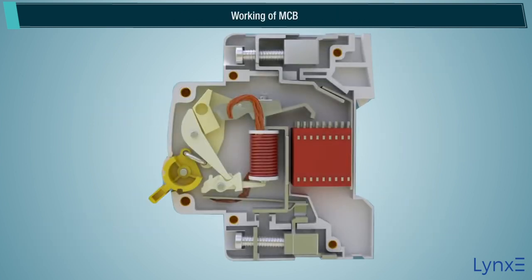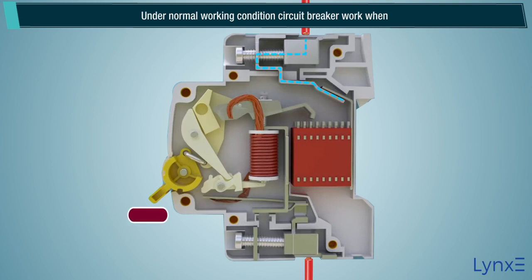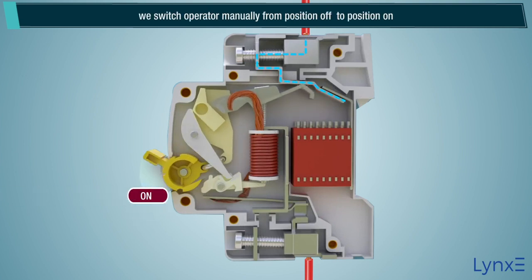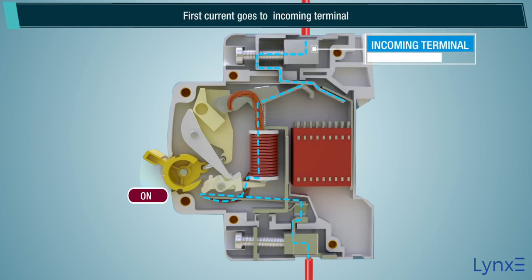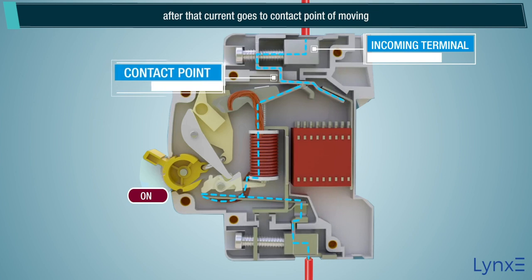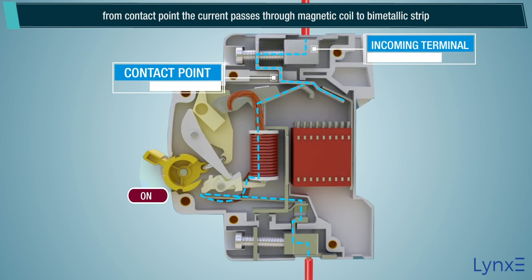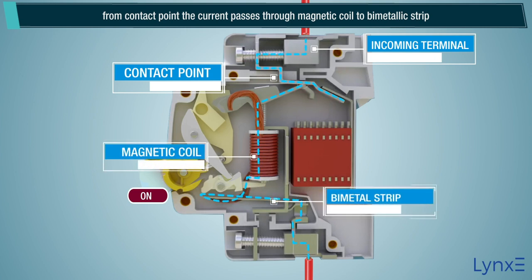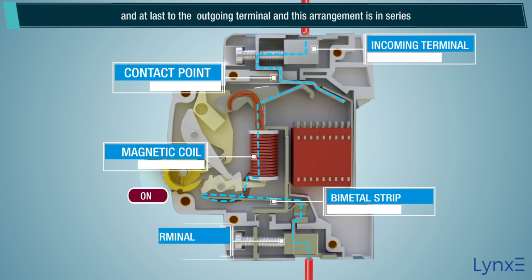Working of MCB. Under normal working conditions, the circuit breaker works when we switch the operator manually from position off to position on. The electric current carrying path is shown below. First, current goes to the incoming terminal. After that, current goes to the contact point of the moving contact. From the contact point, the current passes through the magnetic coil to the bimetallic strip, and at last to the outgoing terminal, and this arrangement is in series.